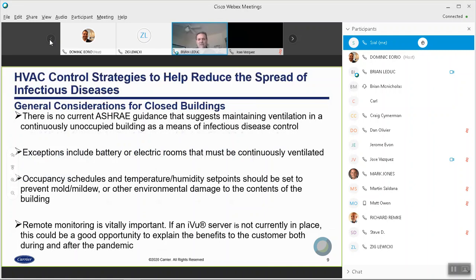So if the facility is going to be shut down for a prolonged period of time, there's really no reason to run ventilation, run the HVAC, unless you've got battery or electrical rooms that do need to be continuously ventilated. You, of course, want to maintain some degree of temperature and humidity control to prevent damage to the building or the contents, but they don't recommend running your equipment 24/7 in an unoccupied building. That doesn't really make any sense, and it's extremely expensive from an energy consumption standpoint.